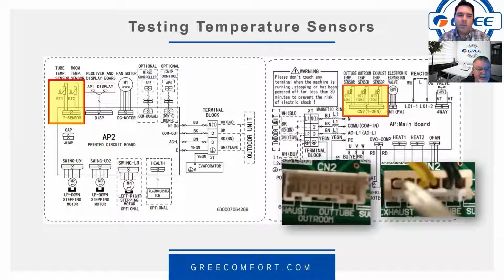I always mention that too, but temperature sensors. Now these are the board diagrams again, showing you where the sensors are located. You'll see that sometimes I'll have the values in here, 15K, 20K, 50K. They don't show that on the indoor, but ambient temperature sensors are always 15K. Tube sensors, evaporator and condenser, are always 20K, and then the discharge sensor is always a 50K. So that kind of helps.